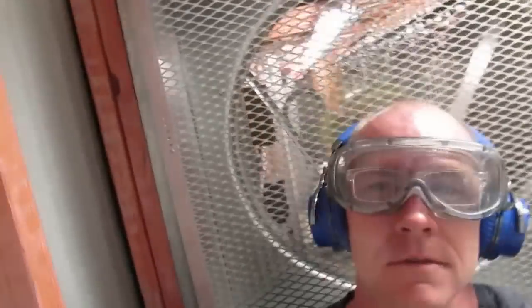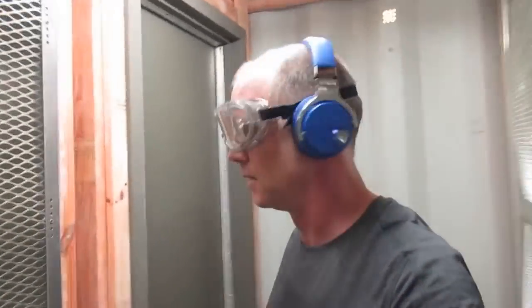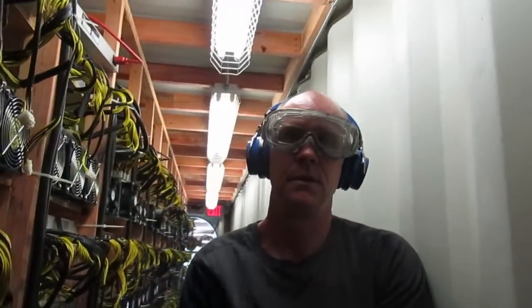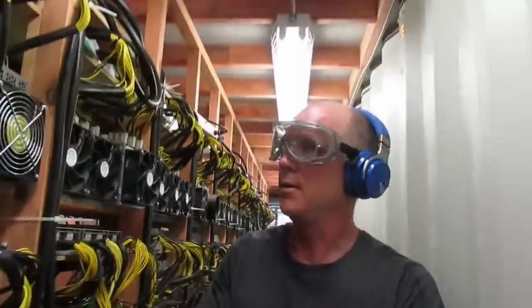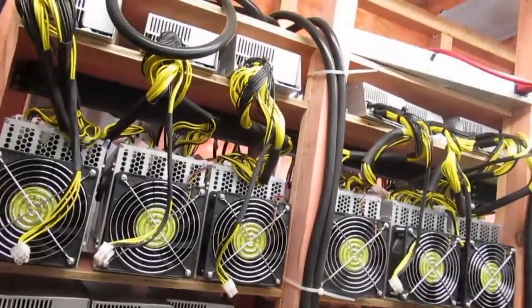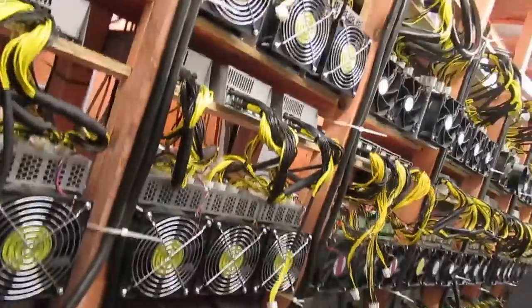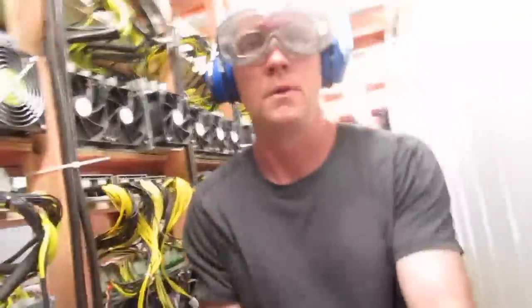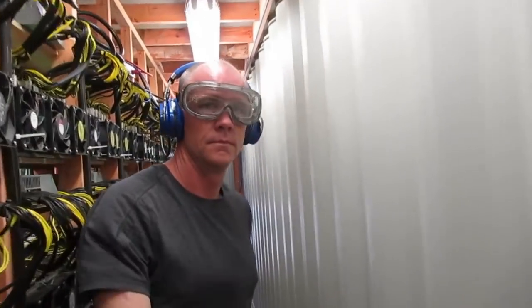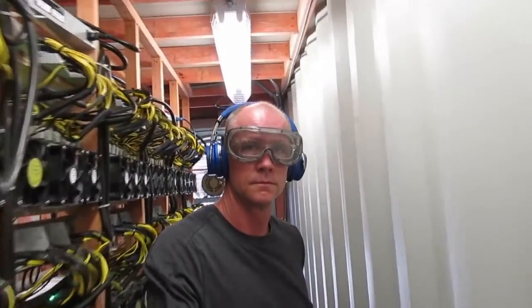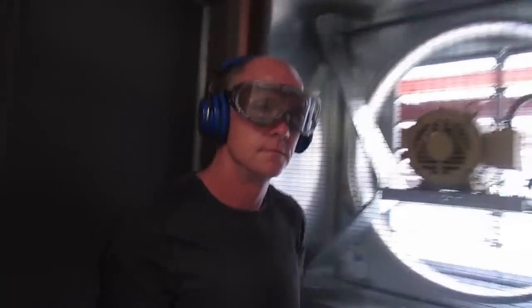Again, they're 20,000 cubic feet per minute, and this is what it looks like from in there. So this has been running for a few months now in the heat, in the rain, in all sorts of different weather, and it's running very reliably. I don't have any recirculation of hot air to the miner intake issues. It is warm on this side. There's about a 30-degree Fahrenheit temperature rise and a corresponding humidity drop as it goes from one aisle to the other. And in here, it's been running, so we're going to keep it running all summer.